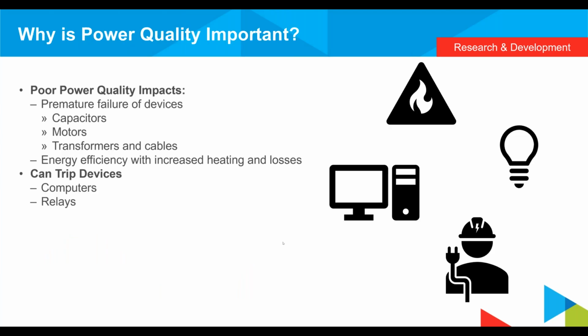So why is it important? What do consumers see when we talk about power quality? Well, poor power quality impacts consumers. It could cause premature failure in end-use devices, whether it's computers, relays, television, light bulbs, capacitors inside electronic appliances, motors inside different equipment downstream, and transformers and cables in between the power grid and the end-use equipment. With poor power quality, there could be premature failures, and there could be increased heating and losses, which will require more generation, but at a lower efficiency. So that is why power quality is important.